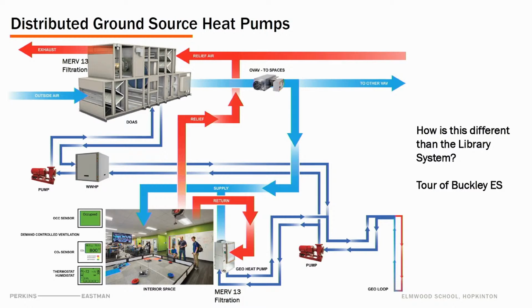Secondary to that, or decoupled from that, is the fresh air system—that's the big box on the left-hand side. It delivers ventilation air to the classroom based on occupancy. If there's a classroom full of students, it'll deliver its maximum amount of fresh air to that space, decoupled from the heat pump system. So the two systems operate independently of each other, and we can control that through occupancy and CO2 sensors and other air quality measures. That's what the system comprises of.